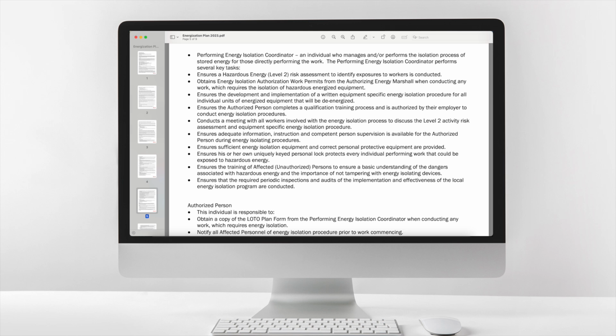Ensures the development and implementation of a written equipment-specific energy isolation procedure for all individual units of energized equipment that will be de-energized. Ensures the authorized person completes a qualification training process and is authorized by their employer to conduct energy isolation procedures. Conducts a meeting with all workers involved with the energy isolation process to discuss the Level 2 activity risk assessment and equipment-specific energy isolation procedure. Ensures adequate information, instruction and competent person supervision is available for the authorized person during energy isolating procedures. Ensures sufficient energy isolation equipment and correct personal protective equipment are provided.